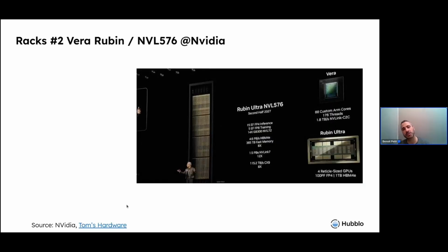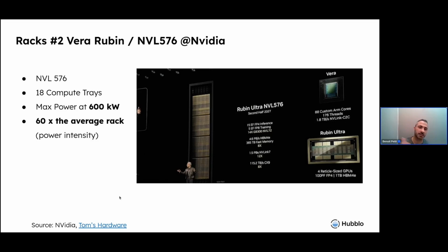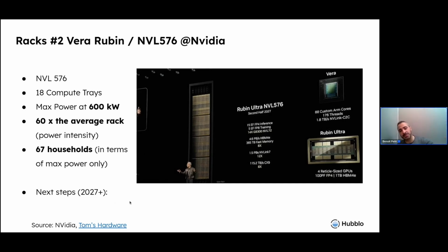And it gets worse if we look at the new announcements based on the Vera Rubin architecture this time and the NVL576 rack. It's still 18 compute trays, but now the maximum power is about 600 kilowatts. So it's 60 times the average rack that we have today if you consider it's about 10 kilowatt per rack, and 67 households if we consider the same comparison. And the next steps after 2027 might be 1 megawatt per rack from NVIDIA. There are already several articles talking about that.